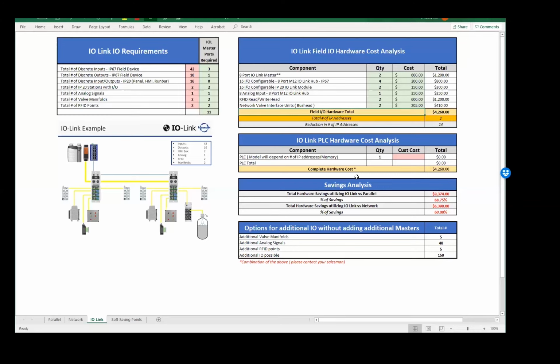One thing too that might add on to what you just said, as you add more IO to your network and your layout, your cost savings is going to increase. Absolutely. So this is going to get even bigger and better the bigger your system starts to lay out. And remember too, with flexibility or addition, the only limitation we're going to have per se in an IO-Link model most of the time is limitation of the hardware. My PLC can only handle so many IP addresses. So while the IO-Link system can handle it, maybe your PLC can't. You have to go to a bigger model. But in terms of flexibility at the field level, IO-Link's there. It's just waiting for something else to be plugged in.